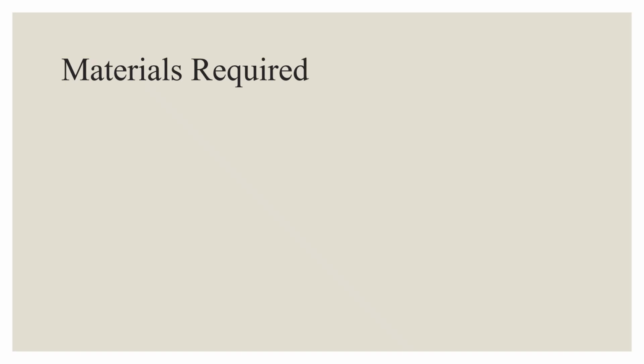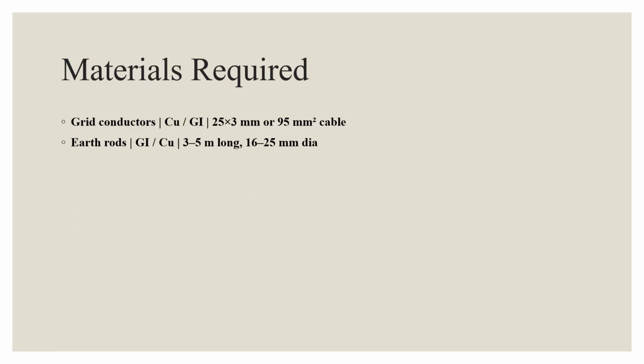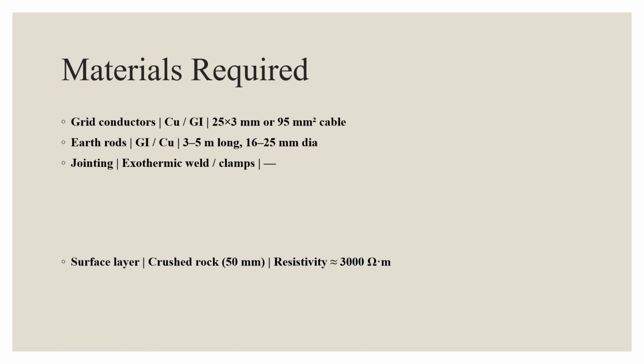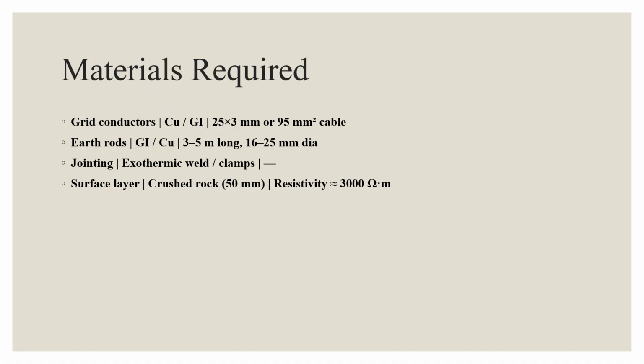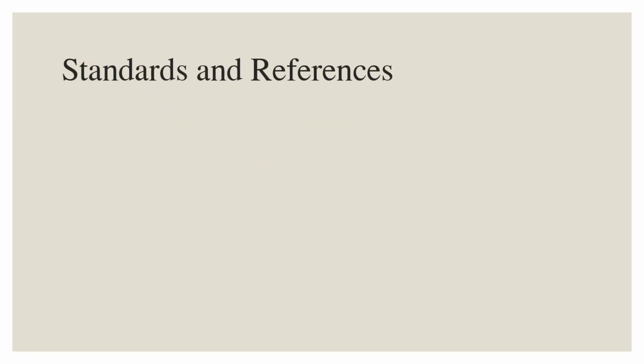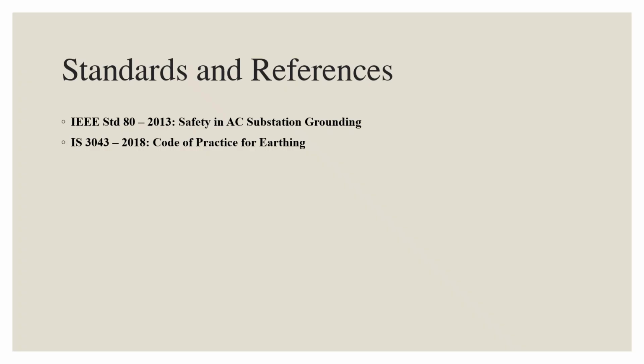The main materials include copper or GI conductors of 25 by 3 mm size or 95 square mm cable, GI or copper rods of 3 to 5 meters, exothermic welding or clamps for joints, and crushed rock for the surface layer. The materials are chosen for strength, conductivity, and corrosion resistance. This design follows international standards: IEEE Standard 80, Safety in AC Substation Grounding, IS 3043, Code of Practice for Earthing, and IEC 60364 for protective conductors and earthing systems. Following this ensures global safety compliance and reliability.